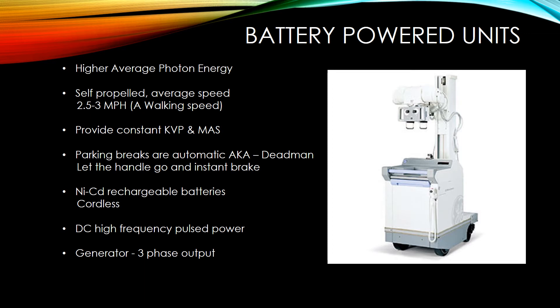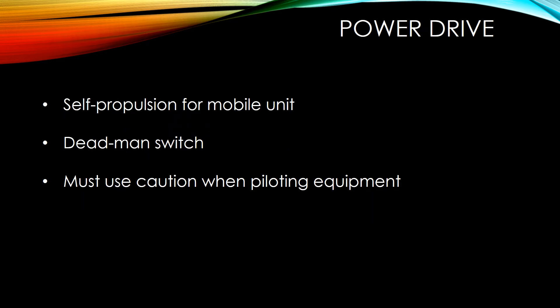Battery-powered units have higher than average photon energy and are self-propelled at the average walking speed of 2.5 to 3 miles per hour, providing constant kVp and mAs. They have automatic parking brakes, also known as dead man brakes — you let go and it's an instant stop. They use rechargeable batteries, DC high frequency pulse power, and a generator with three-phase output. The power drive is a self-propulsion unit with a dead man switch, and you must use caution when piloting.